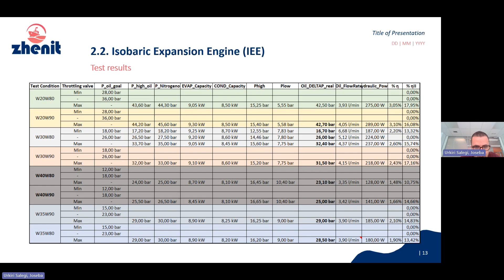As I mentioned, in a work output hydraulic module, we have a hydraulic accumulator in the high pressure line. And this hydraulic accumulator, we see that it is very important and has a very positive impact on flow stability. If the charge of nitrogen is not the correct one, I mean, if we have a low pressure of nitrogen or a high pressure of nitrogen, the accumulator doesn't have the capacity to guarantee us a stable flow. So it was difficult to define the correct nitrogen pressure, but finally we reached it.